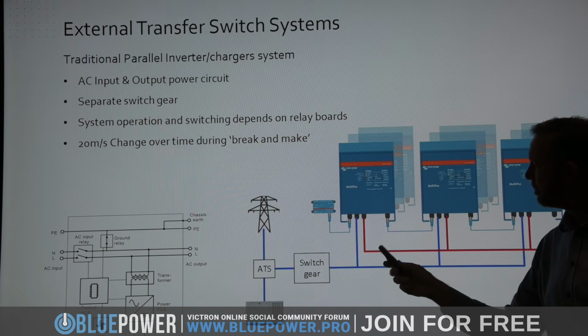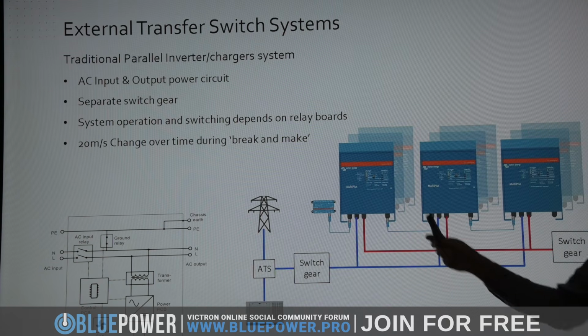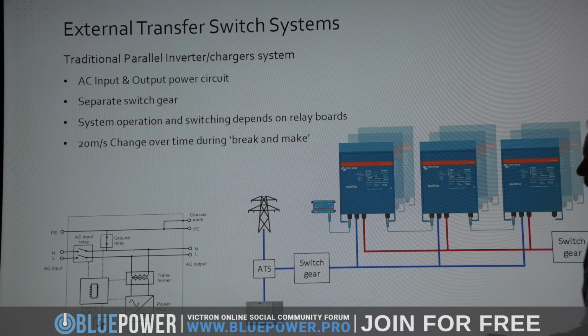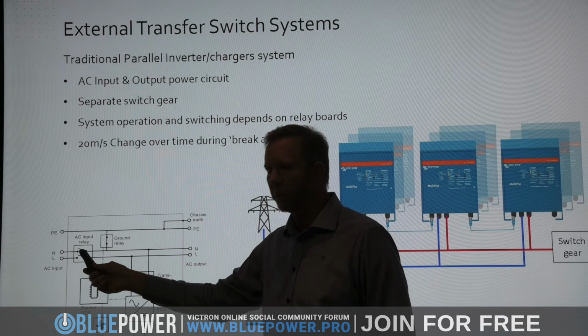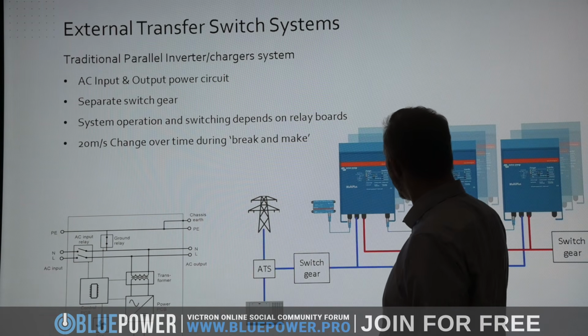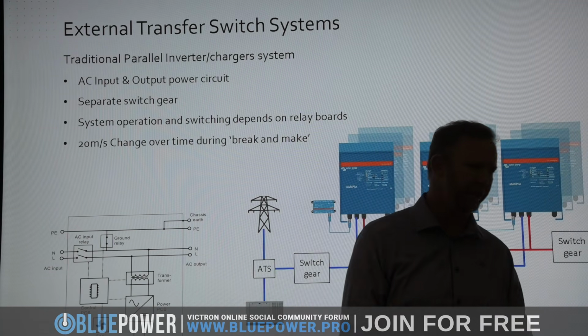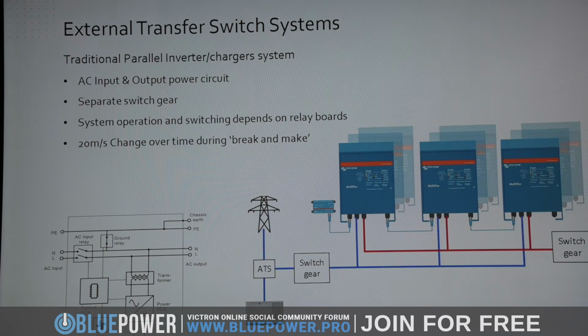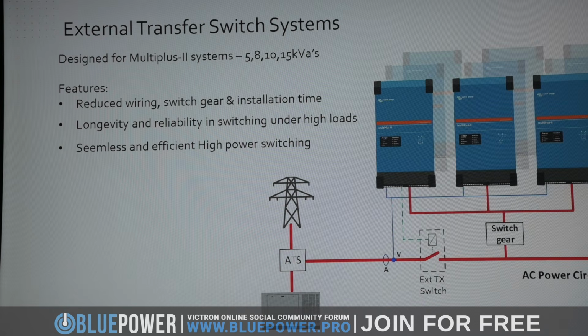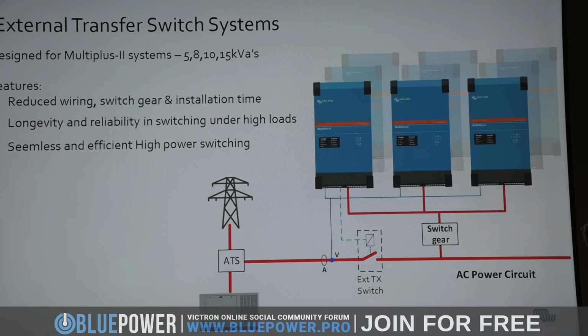The problem here is, well, it's not a problem, but the reality is that in every Multiplus in the system, the internal transfer switch will operate. And the units all have to communicate so they all switch at the same time. Depending on the loads, the power factor, how clean the power is, and reliability, over time that gets worse, which means the relays operate. They take strain, they can only do so much, and that's usually the first thing that fails. So that's why we've developed the external transfer switch topology, and that's what all the big guys are doing.